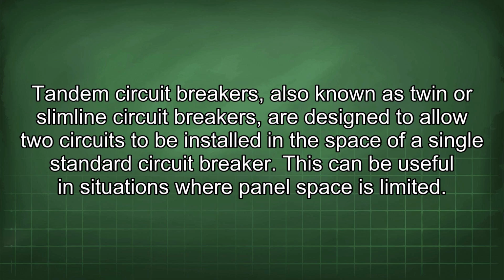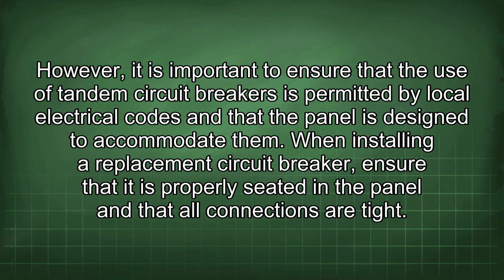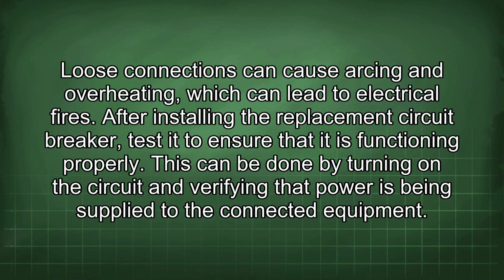equipment. Tandem circuit breakers, also known as twin or slimline circuit breakers, are designed to allow two circuits to be installed in the space of a single standard circuit breaker. This can be useful in situations where panel space is limited. However, it is important to ensure that the use of tandem circuit breakers is permitted by local electrical codes and that the panel is designed to accommodate them. When installing a replacement circuit breaker, ensure that it is properly seated in the panel and that all connections are tight. Loose connections can cause arcing and overheating, which can lead to electrical fires.